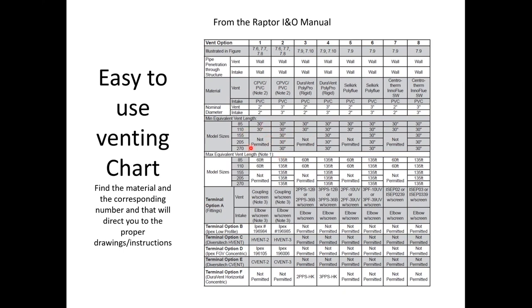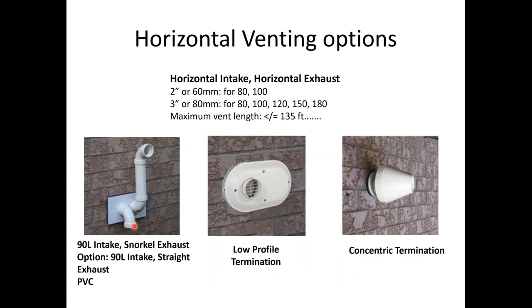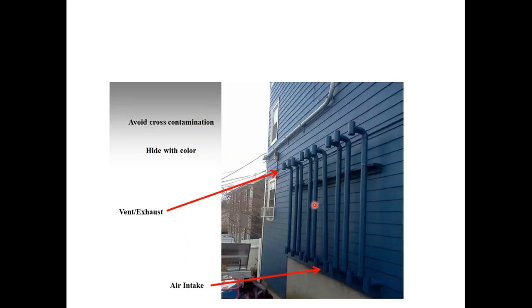are going to be 30 inches for them, and that's mostly for noise. If it's shorter than 30 inches, sometimes we have to figure some things out. They do get a little rowdy on initial light off, but hopefully you have at least a 30-inch vent length. Some of our options, you have snorkel that originally was only for PVC. They do have UV rated polypropylene now, so you can snorkel polypropylene. Your low profile terminations and your concentric terminations. You can use the same plane and just raise the exhaust higher than the air intakes to prevent cross contamination.